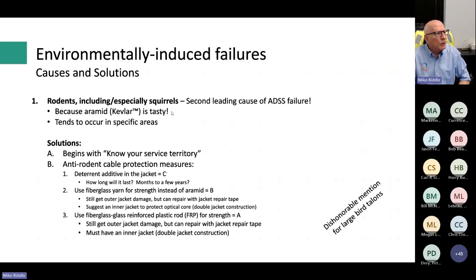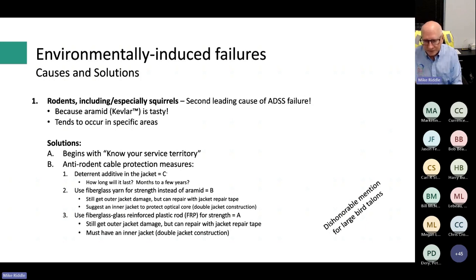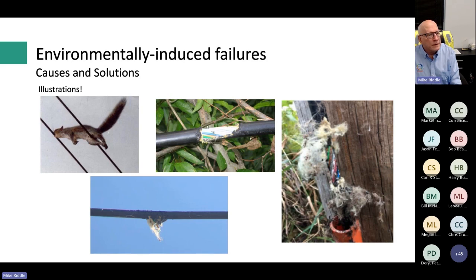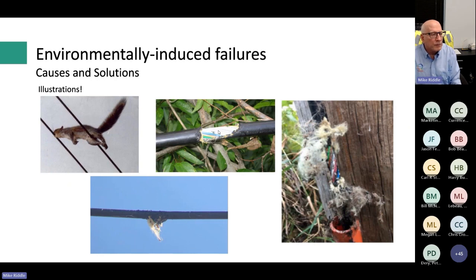Some utilities have also had problems with large birds of prey like hawks whose talons can pierce the outer jacket and cause problems. Pictures of rodent damage show animals have chewed through the outer jacket and damaged the strength member. Even where buffer tubes aren't fully chewed through, failure is likely because water will eventually get through the plastic.